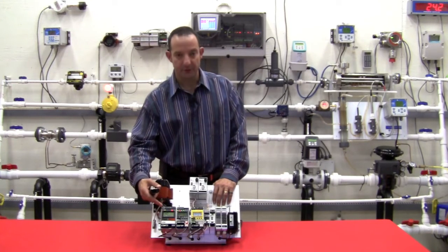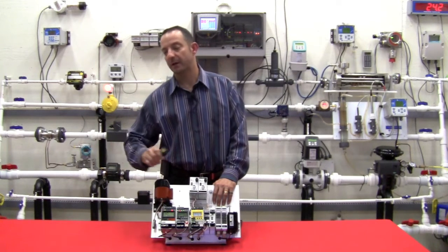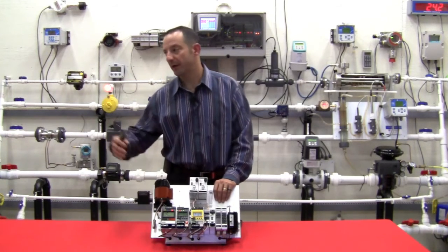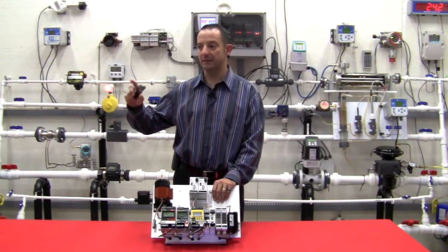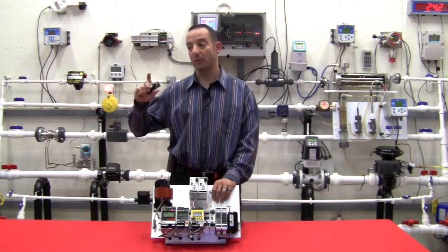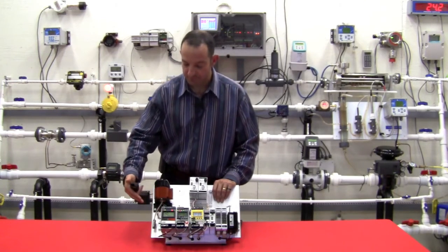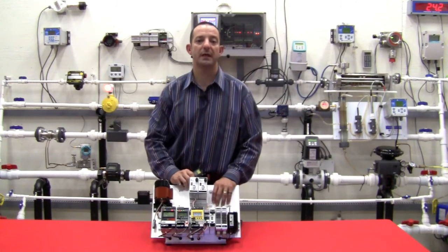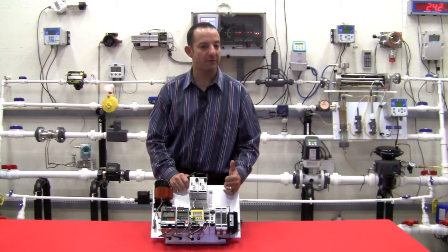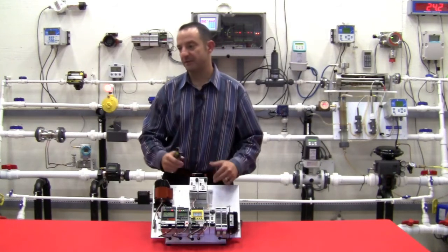Specifically, a HART loop has often up to 4 variables of data encoded in the digital data stream coming from the HART protocol transmitter, but an analog input card on a control system is only capable of looking at the DC analog current, or as we say, the primary variable in the loop. So what the HIM does is it wires across the loop and looks at that digital communication and extracts the secondary variable, the tertiary variable, and the 4th variable from that device.